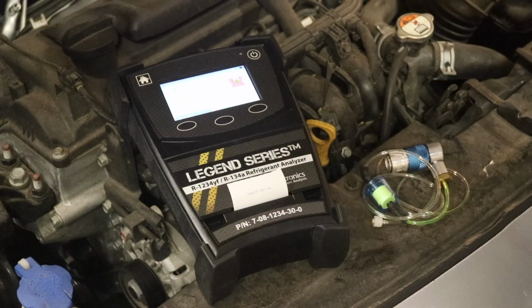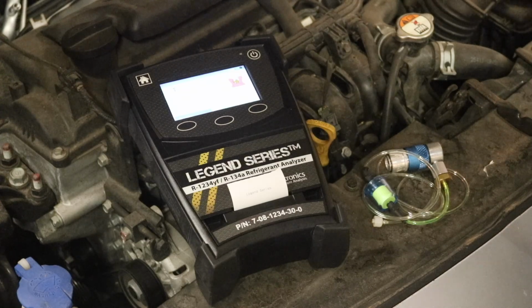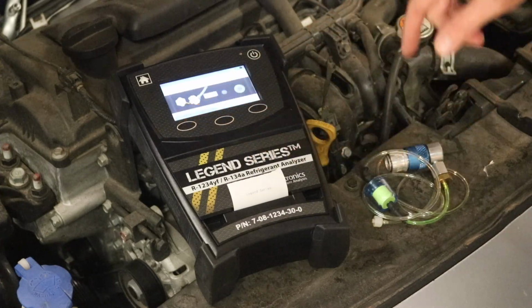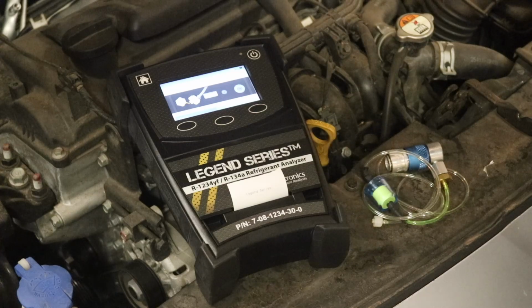Now importantly, making a choice here helps the machine know where to start with the algorithms internally, but ultimately it will look for all refrigerants when it breaks down that chemical makeup of the sample charge. So let's choose R134A. The instructions are quite clear on the screen.